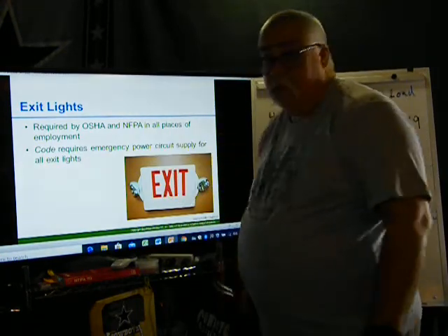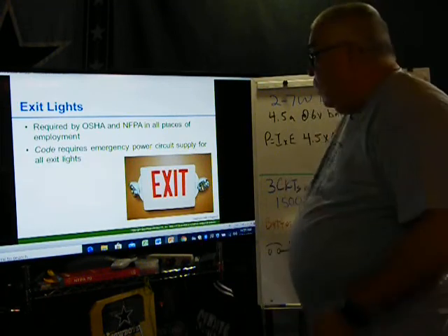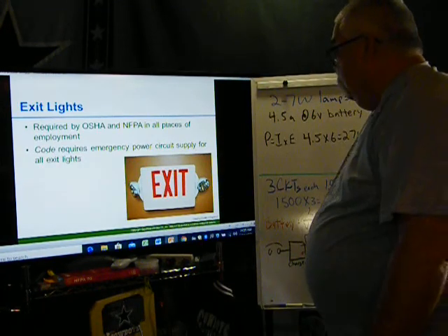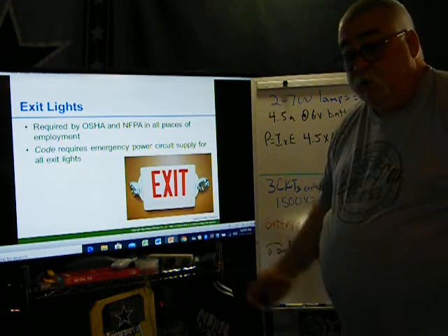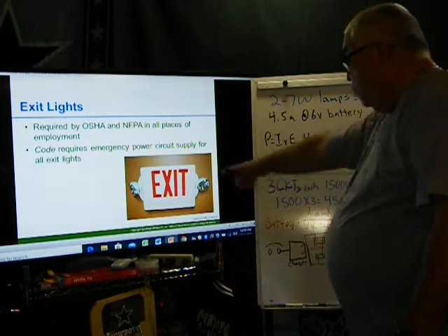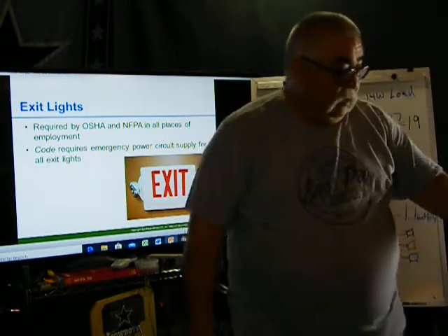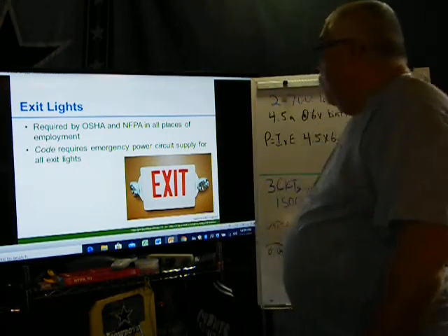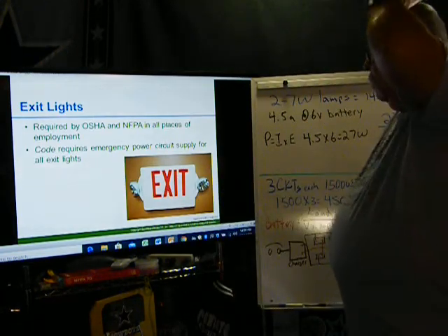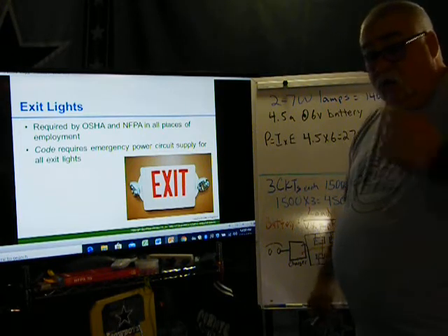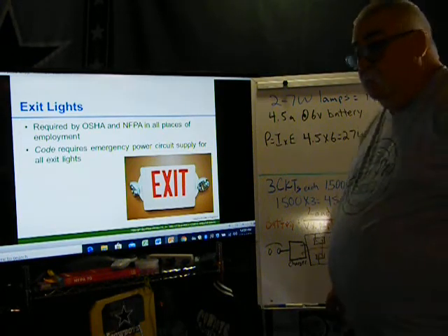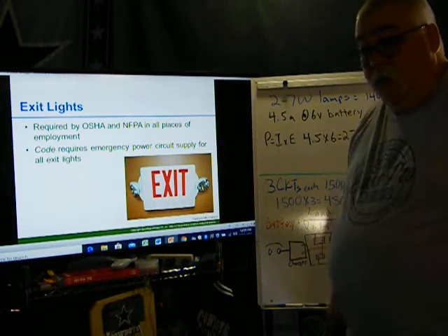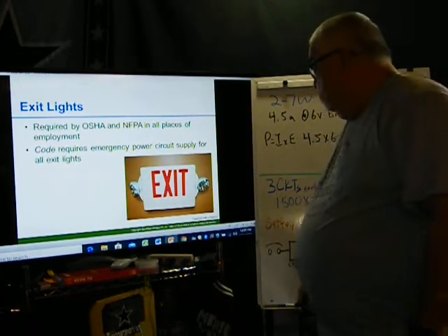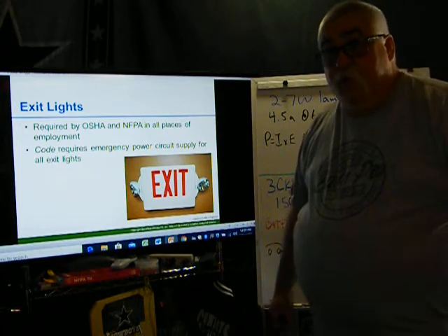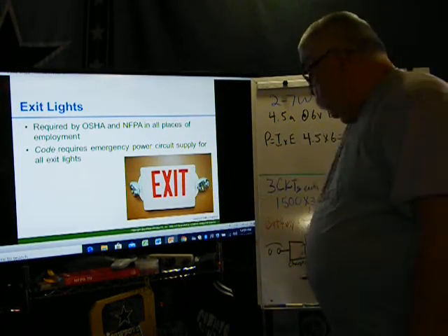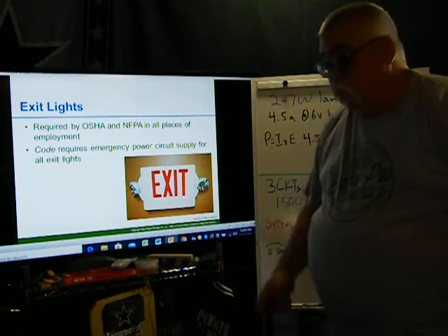All you've got to do is check and make sure the battery can handle that hour and a half. And they don't have to be wired, no generators or anything are needed. No batteries to add, why? Because the battery's internal, just like this bug light that I showed you. Code requires an emergency power circuit supplied for all exit signs, unless it's got a battery inside. If you don't have a battery and you're just using one that's powered up, then you're going to have to put in some type of system to run these, whether you use batteries or a generator.